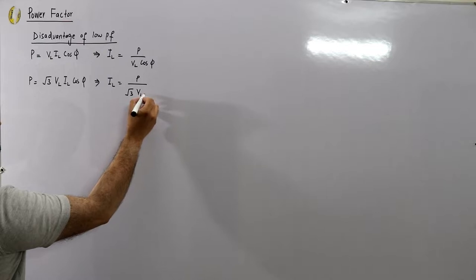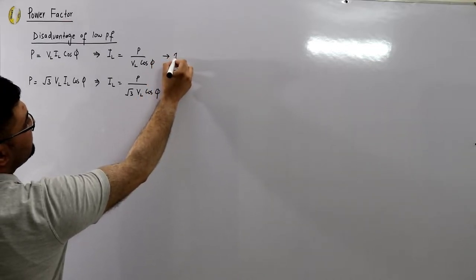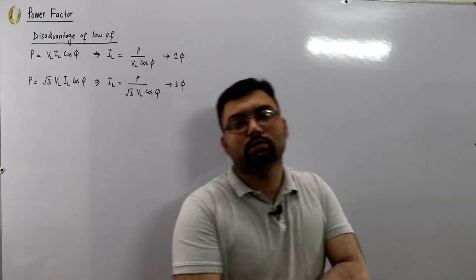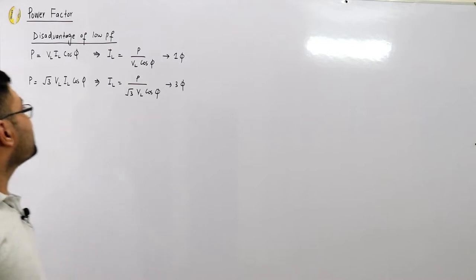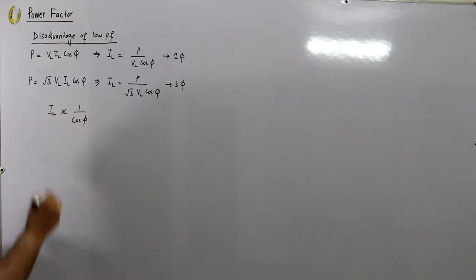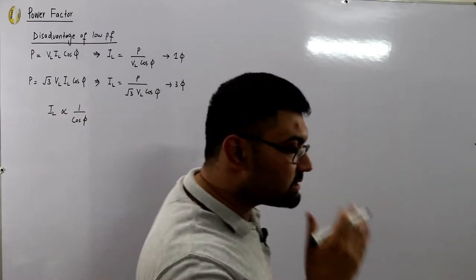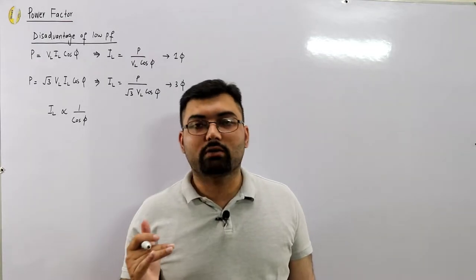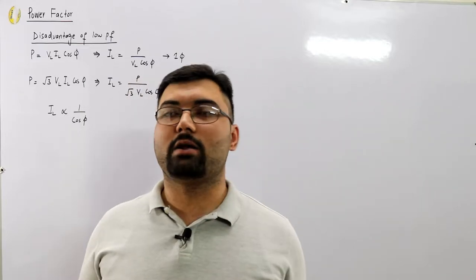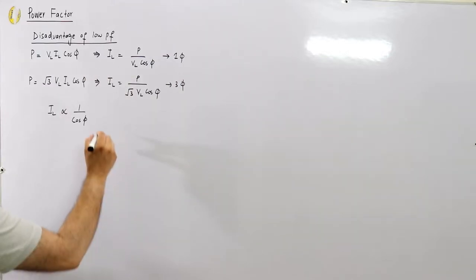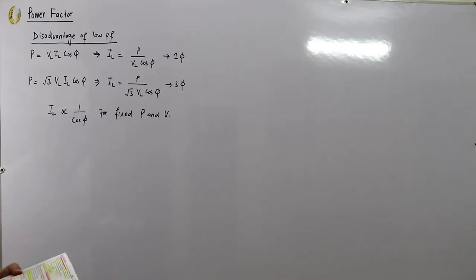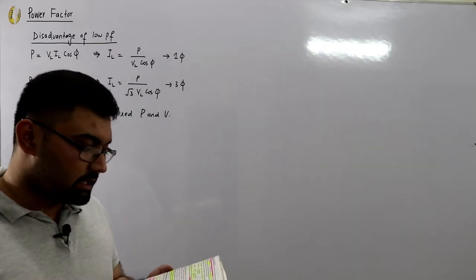In both single-phase and three-phase cases, the line current IL is inversely proportional to the power factor cosφ. For a fixed value of power and voltage, lower power factor means higher load current, and vice versa.